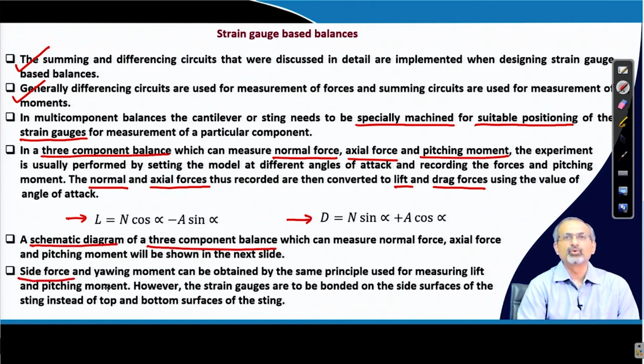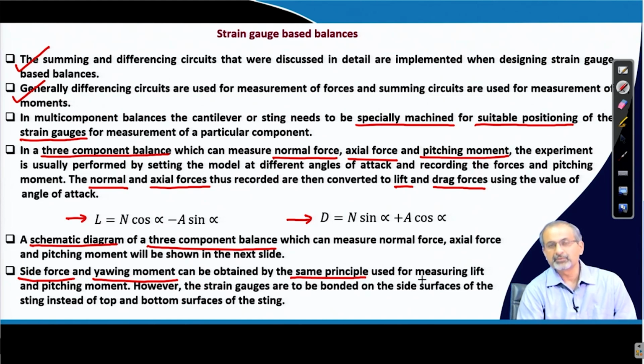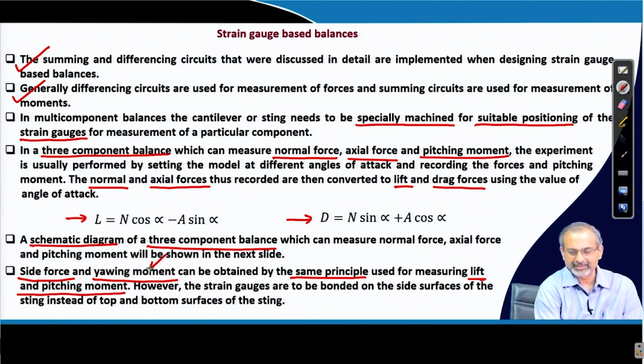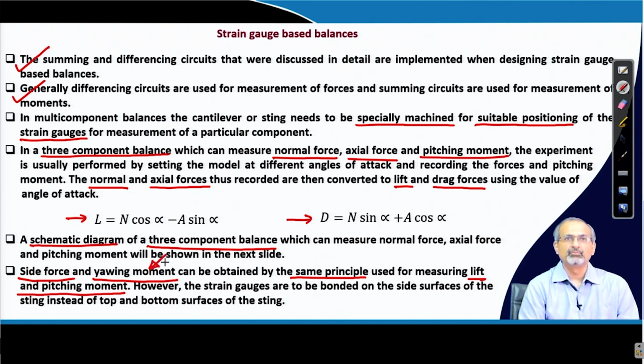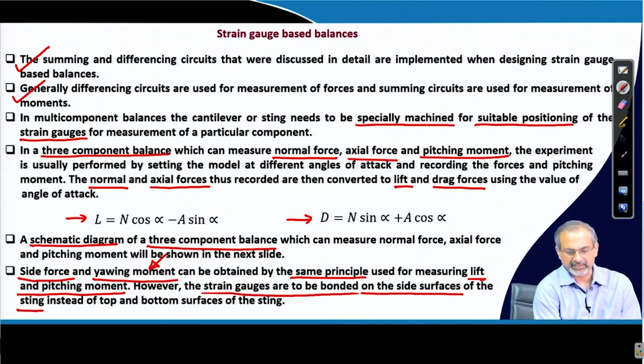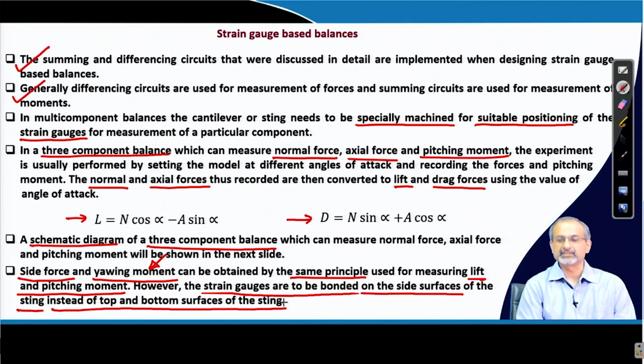If you want to measure still more components, say side force and yawing moment, the same principle gets extended. Whatever principle is used for measuring lift and pitching moment extends to side force and yawing moment measurement, except that the strain gauges are bonded on the side surfaces of the sting instead of the top and bottom surfaces.